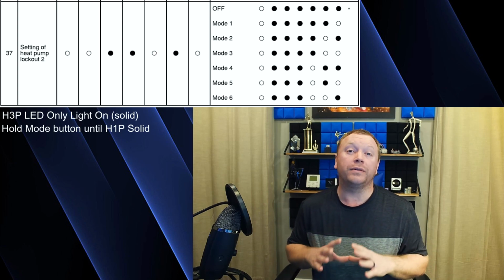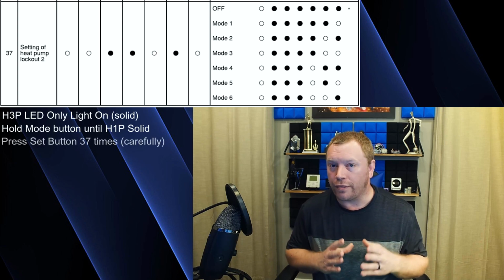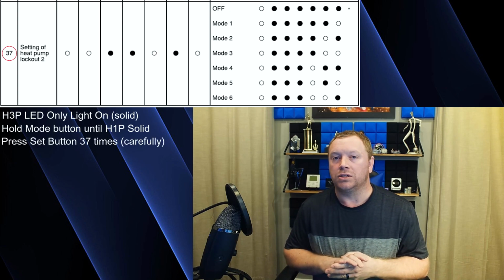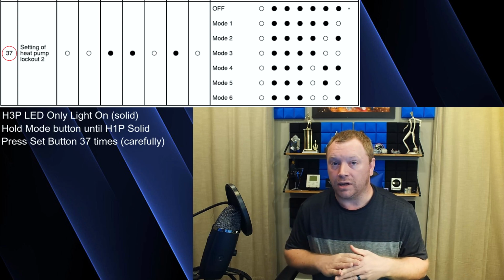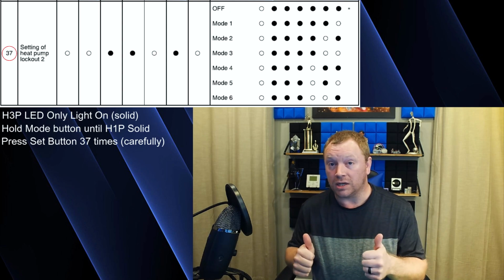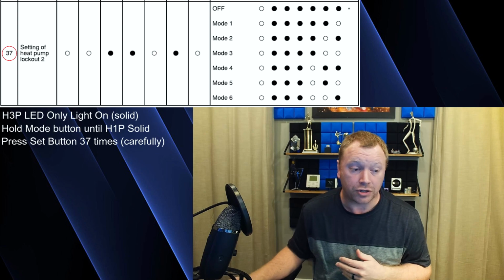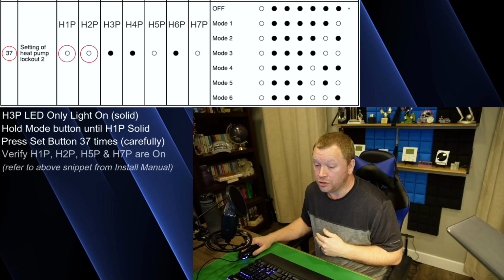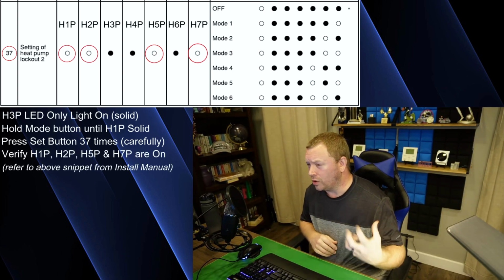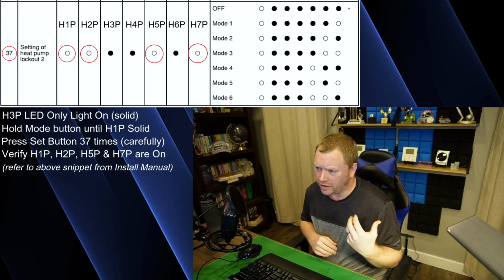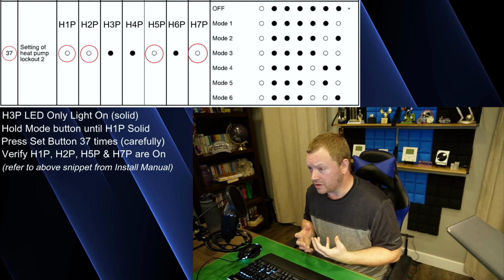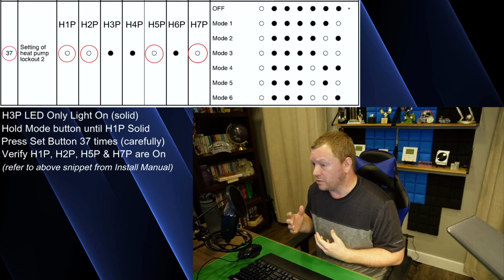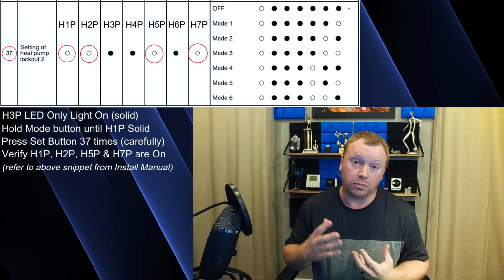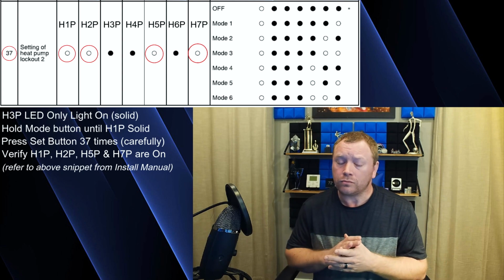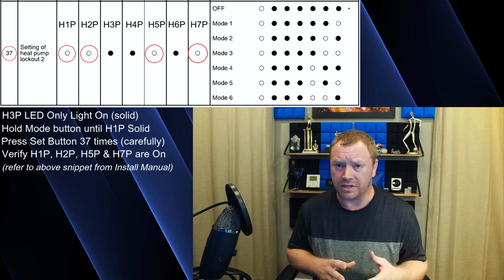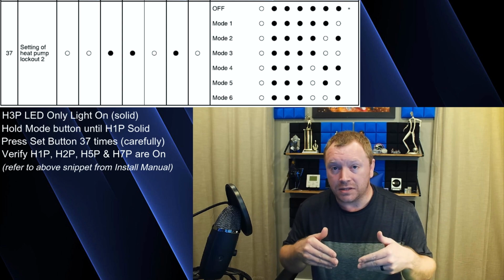That is your indication that you are in the service mode. Now you're going to very carefully press the set button 37 times. So 37, if you know how to count up the binary LED, awesome. And if you don't, the lights that you need to make sure are on are going to be 1, 2, 5, and 7. 1, we don't count that value. 2 is a value of 32. 5 is a value of 4, and 7 is a value of 1. So if you add up 32 plus 4 plus 1, you get to 37.